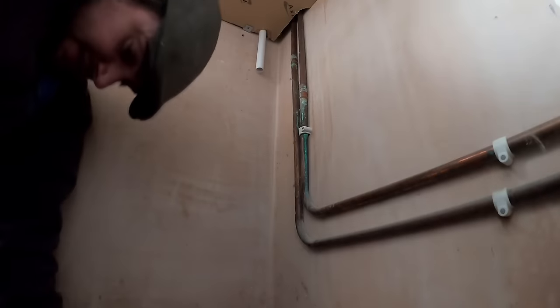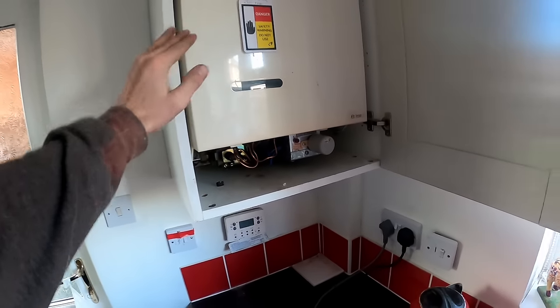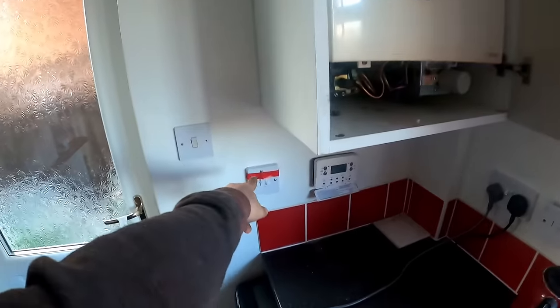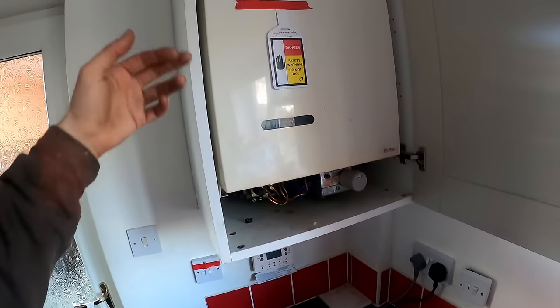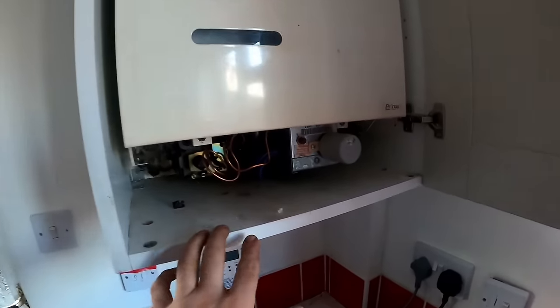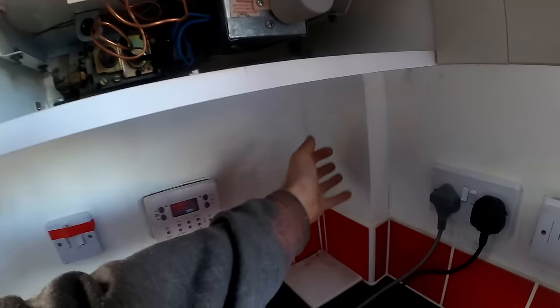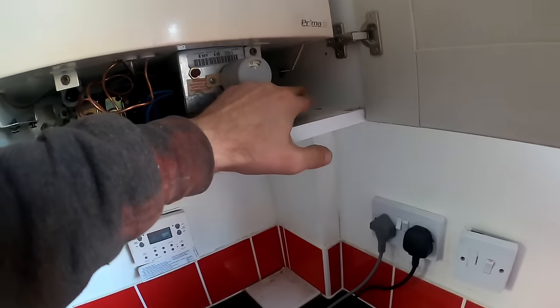Welcome to my office. Today's job is changing a Potterton Prima — the heat exchanger is leaking. It's been capped off, the fuse has been removed, and the gas has been isolated. I'm taking the cupboard down and putting it back to 16mm. The gas is 22mm where it leaves the meter.